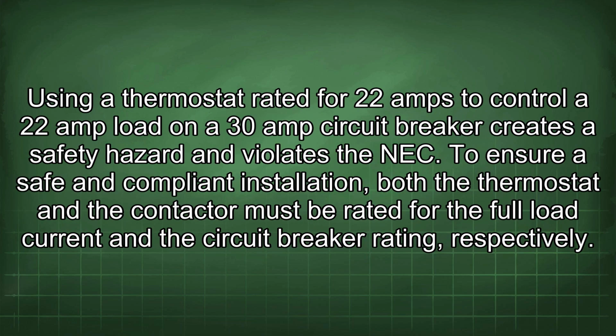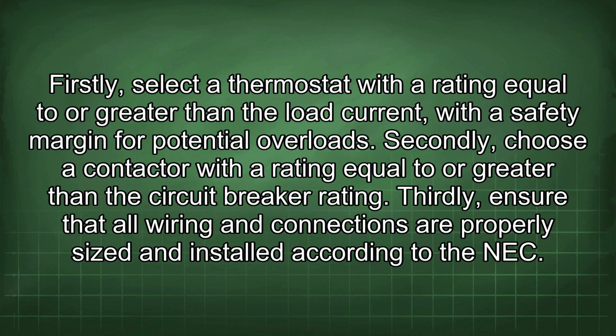Using a thermostat rated for 22 amps to control a 22 amp load on a 30 amp circuit breaker creates a safety hazard and violates the NEC. To ensure a safe and compliant installation, both the thermostat and the contactor must be rated for the full load current and the circuit breaker rating, respectively. Firstly, select a thermostat with a rating equal to or greater than the load current, with a safety margin for potential overloads.